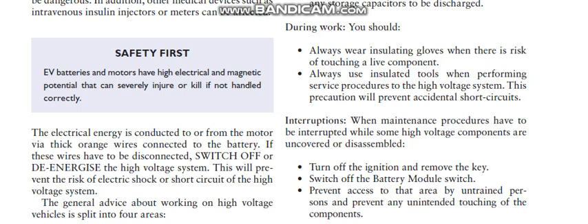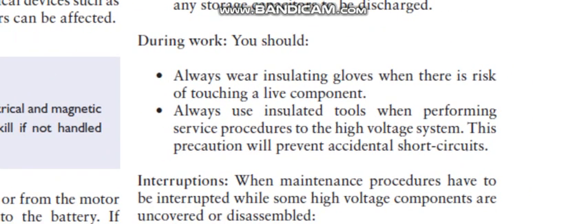Before work, you must turn off the ignition switch and remove the key. Switch off the battery module switch or de-energize the system. Wait for 10 minutes before performing any maintenance procedures on the system. This allows any storage capacitors to be discharged.